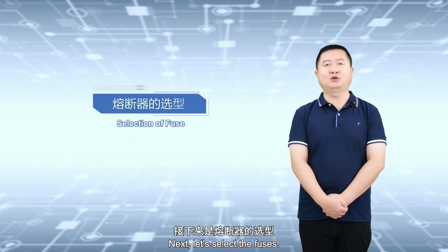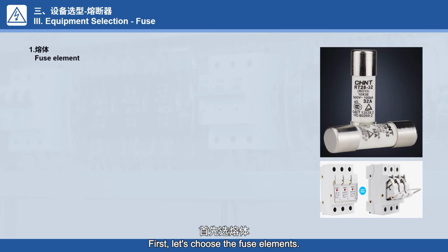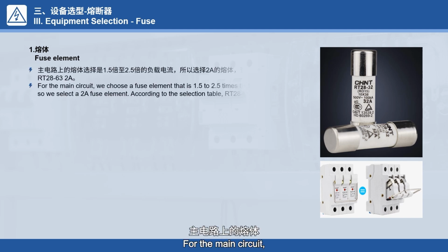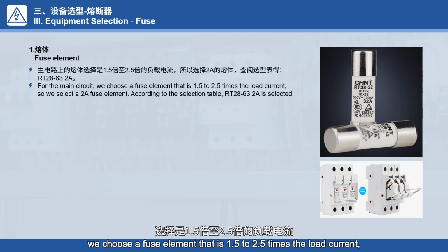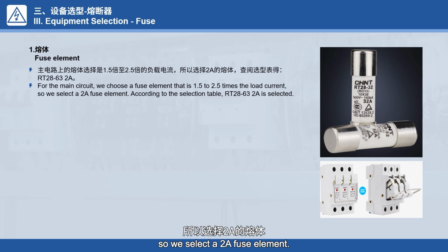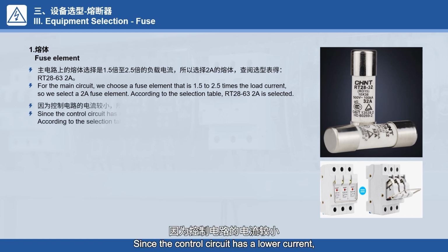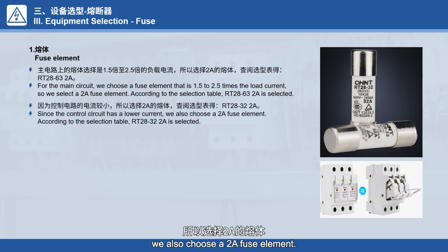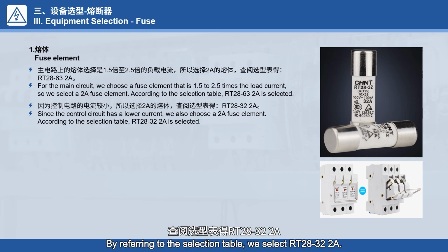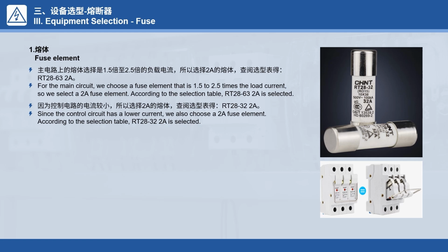Next, let's select the fuses. First, let's choose the fuse elements. For the main circuit, we choose a fuse element that is 1.5 to 2.5 times the load current. So we select a 2A fuse element. By referring to the selection table, we select RT28-63 2 amperes. Since the control circuit has a lower current, we also choose a 2A fuse element. By referring to the selection table, we select RT28-32 2 amperes.